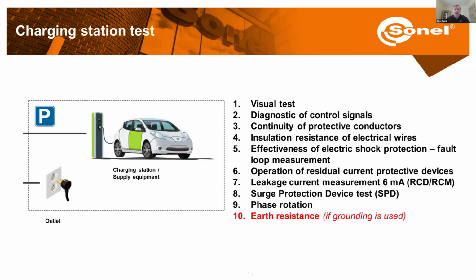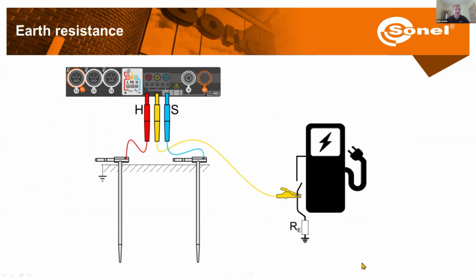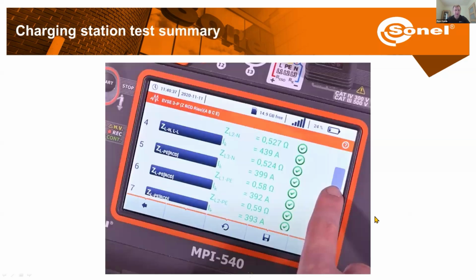Okay, and finally, earth resistance measurement, but that's only in case the charging station has its own independent grounding. In case the charging station is, for example, in some garage, in a building, then we just need to check continuity to make sure that the earthing of the charging station is connected correctly with the earthing of the entire building. But when the charging station has earthing of its own, we need to perform the tests. Depending on the meter, we have different tests available. Here I have an example with the test where we are using rods. Oh yeah, and these are all of the tests that we need to perform for charging stations. The meters allow you to create a sequence of different tests, which are performed later automatically. And at the end, you can see the summary of the results.